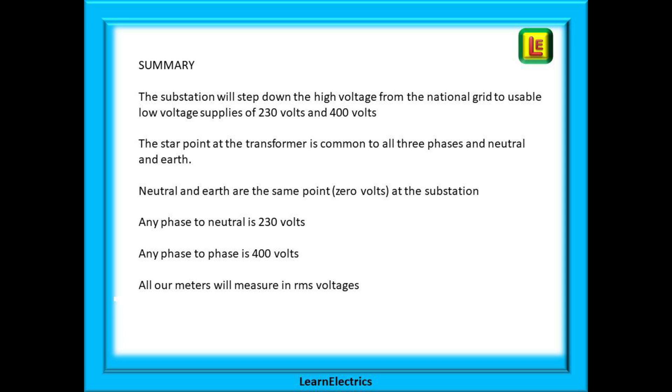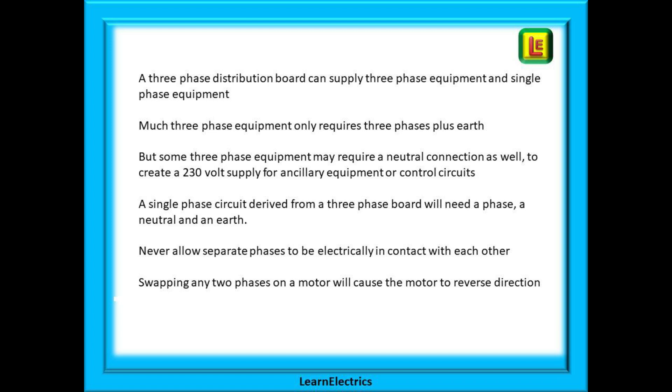Remember also that our test meters will measure in RMS voltages. A three-phase distribution board can supply three-phase equipment and single-phase equipment. Much three-phase equipment only requires three phases plus earth. But some three-phase equipment may require a neutral connection as well to create a 230 volt supply for ancillary equipment or control circuits. A single-phase circuit that is derived from a three-phase board will need a phase, a neutral and an earth. Never allow separate phases to be electrically in contact with each other. And swapping any two phases on a motor will cause the motor to reverse direction.